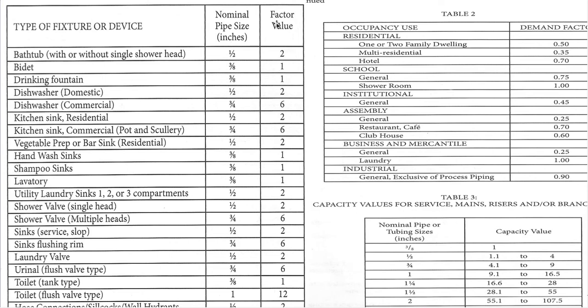So you get your factor values from all your fixtures, multiply it by your demand factor, and you come down here under Table 3 — your service mains and risers or branches, depending on what you're sizing. Come to your capacity value and then find where it lies between the two columns.